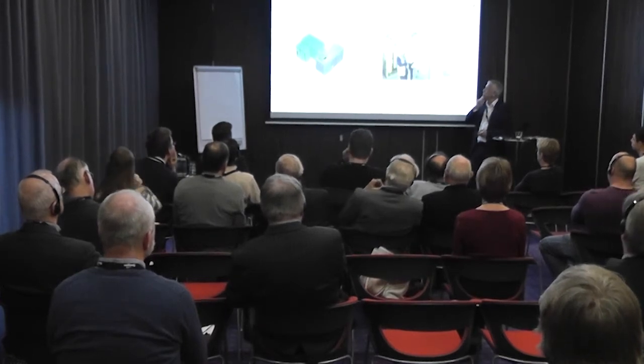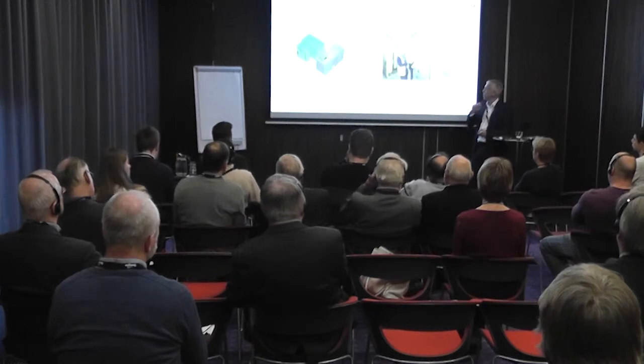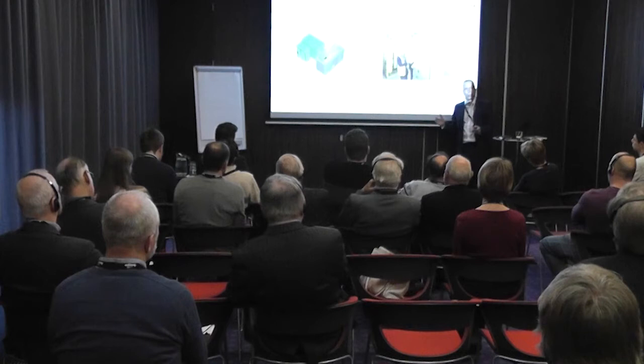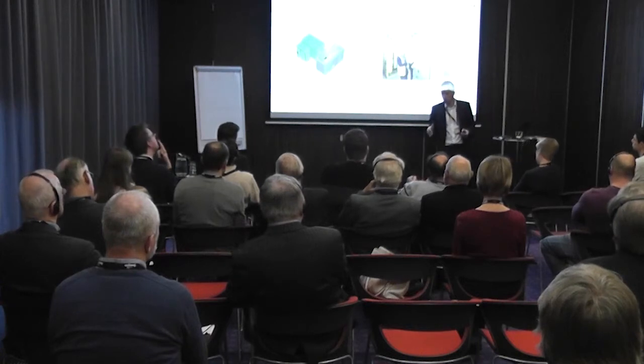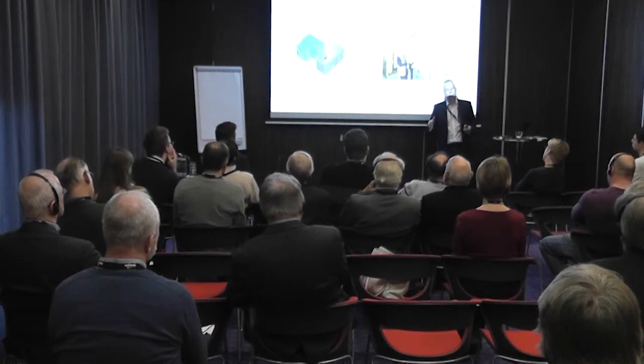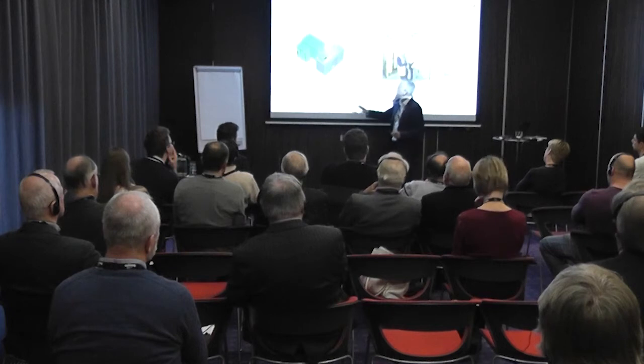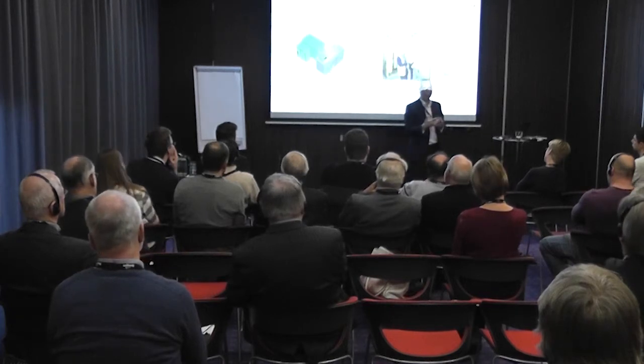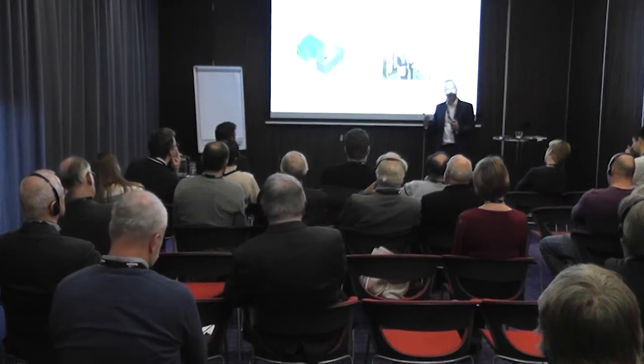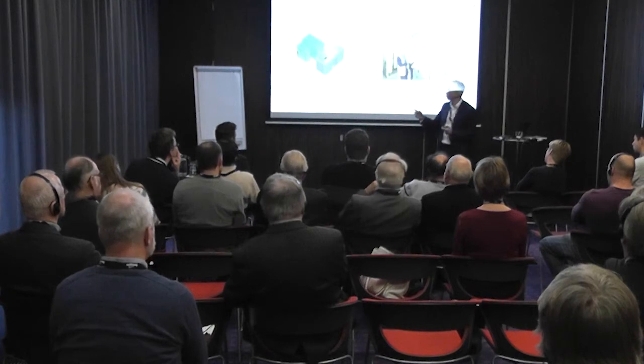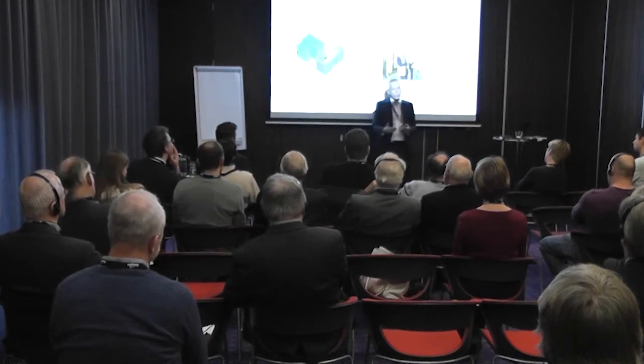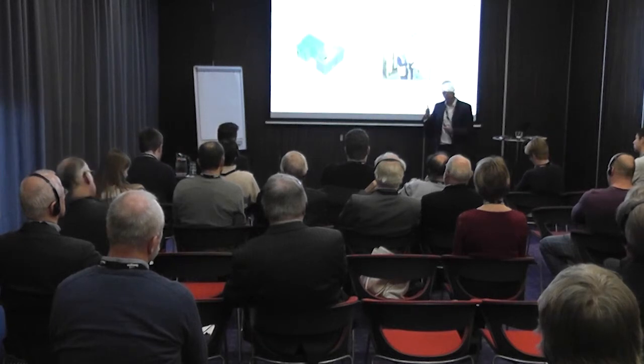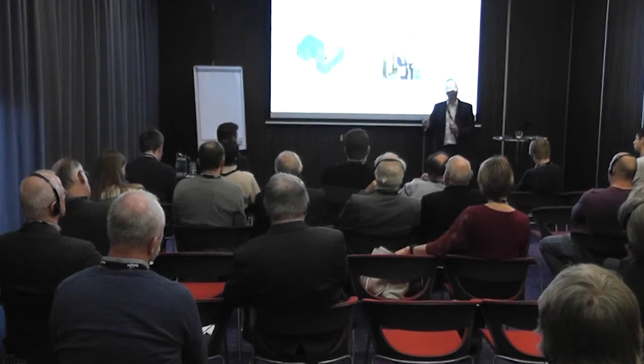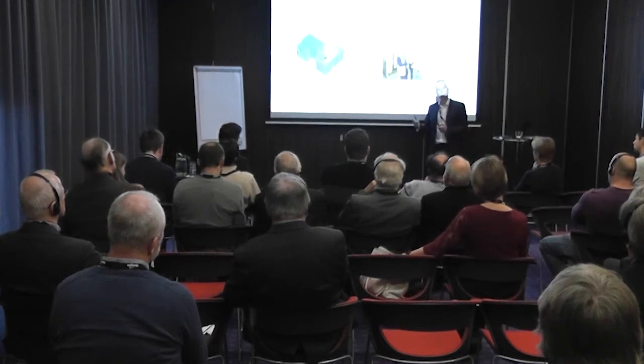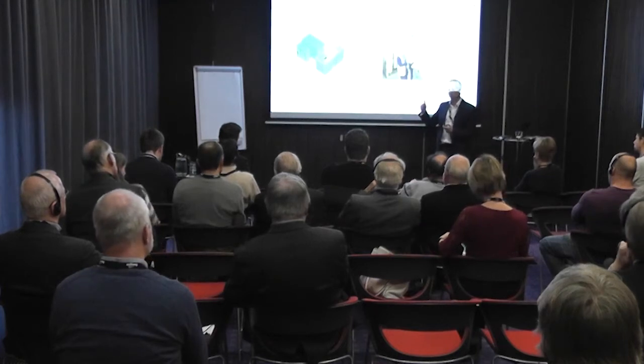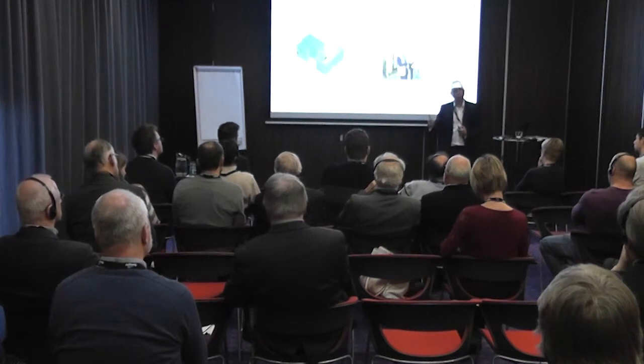One low zero carbon technology we apply to this building is a fuel cell. A fuel cell is interesting technology - I'm not going to go into the specific details, but inside the unit you have a chemical reaction driven by natural gas. So this fuel cell is supplied with natural gas, the chemical reaction generates electricity and also generates waste heat, and that waste heat is what we use for driving absorption chillers and also heating and hot water in the building.